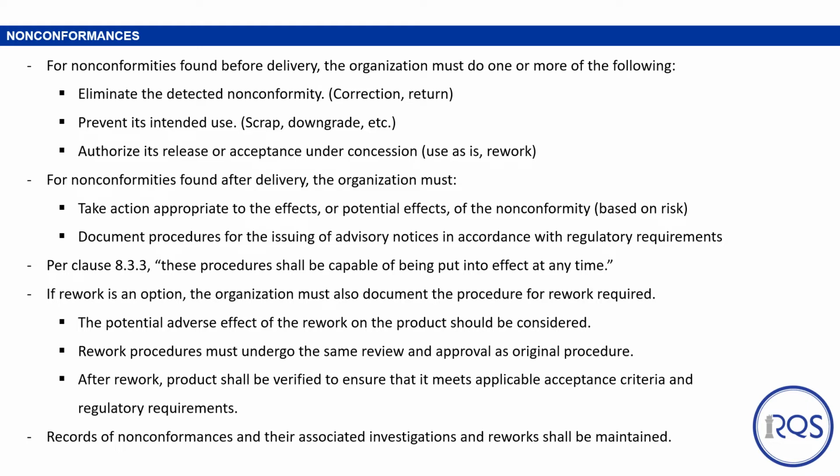If rework is an option, the organization must also document the procedure for rework required. The potential adverse effect of the rework on the product should be considered. Rework procedures must undergo the same review and approval as the original procedure. After rework, product shall be verified to ensure that it meets all applicable acceptance criteria and regulatory requirements. Records of nonconformances and their associated investigations and rework shall be maintained.